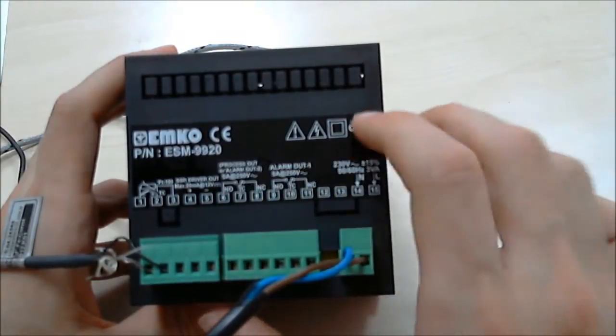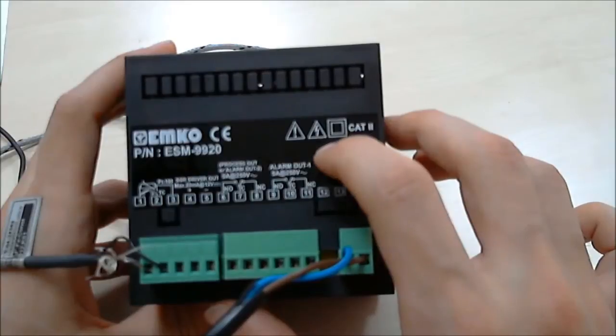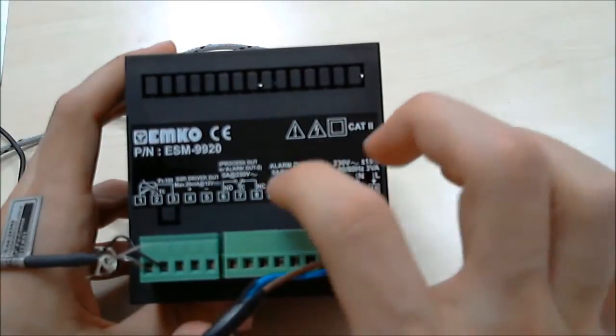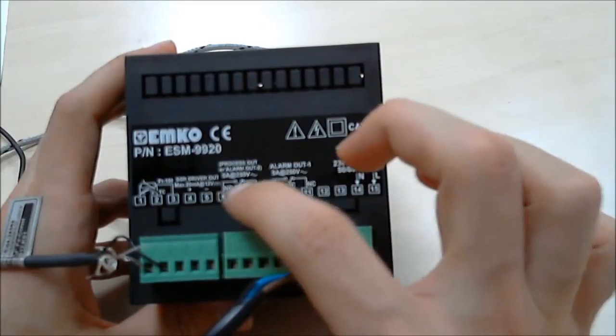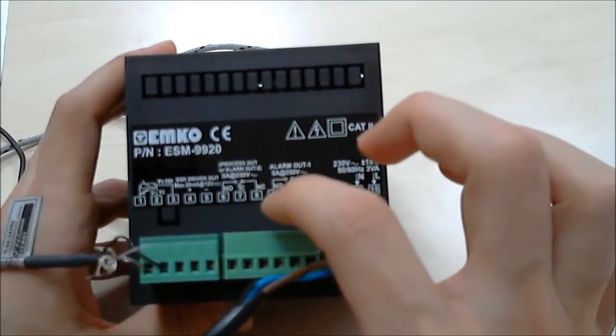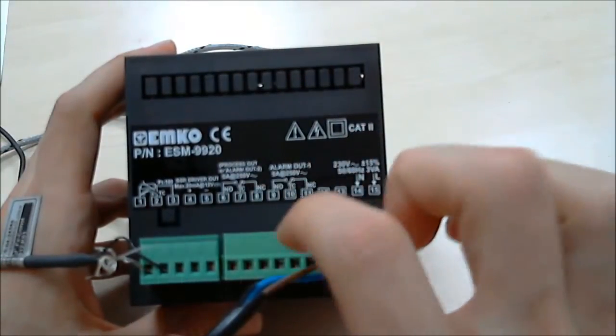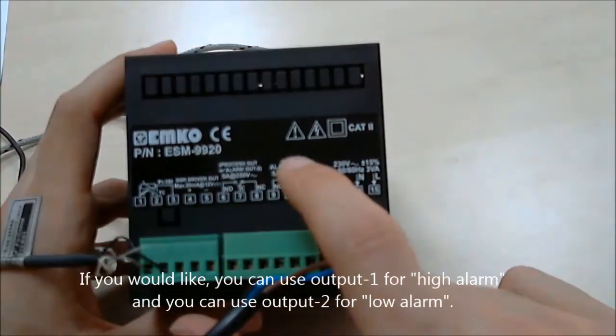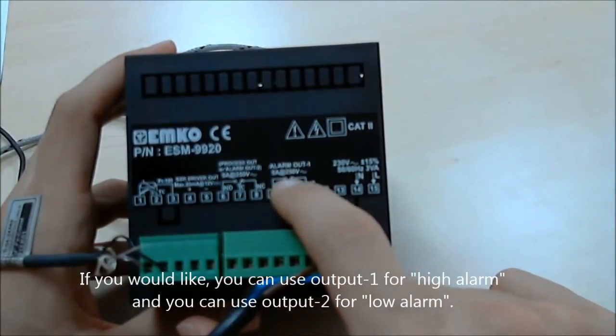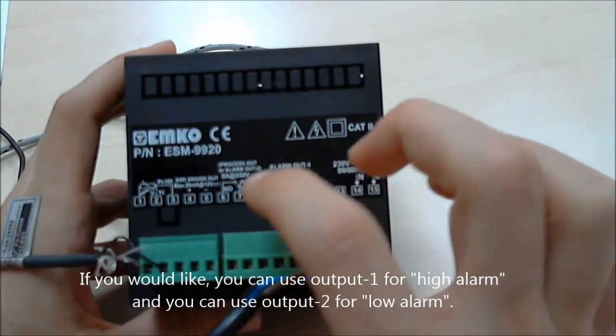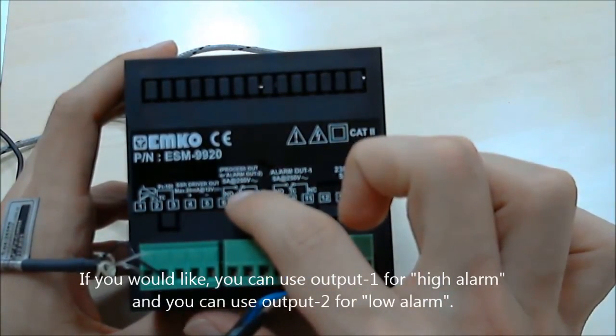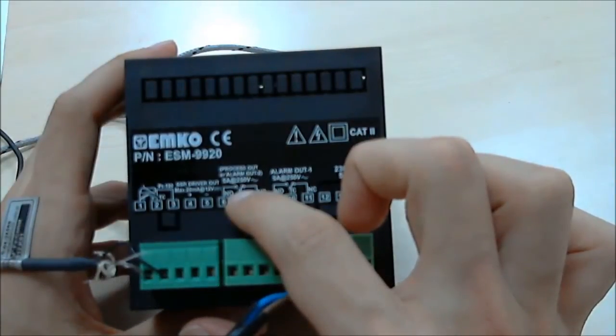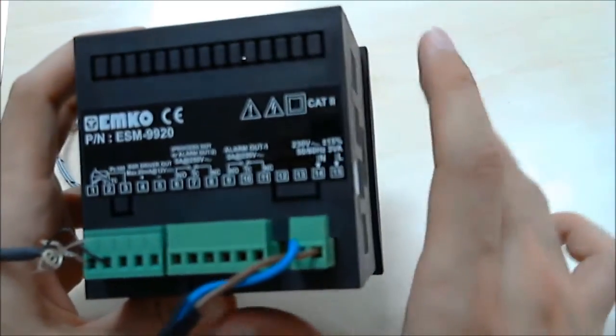But if you select SSR output control by parameters, you can use two outputs together. So you can use alarm output 1 for high process alarm, and you can use alarm output 2 for process output or low alarm control.